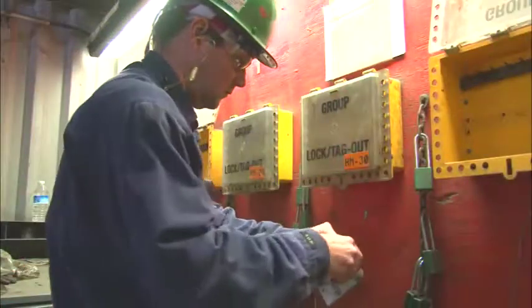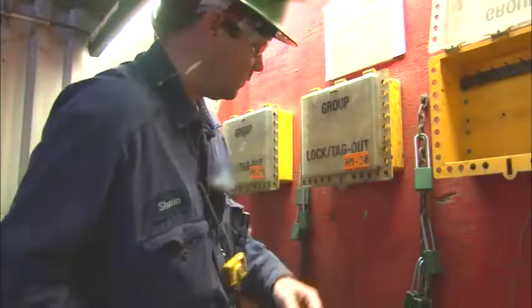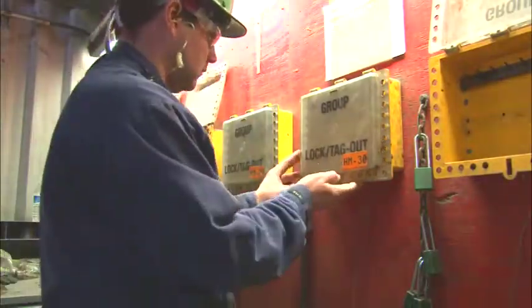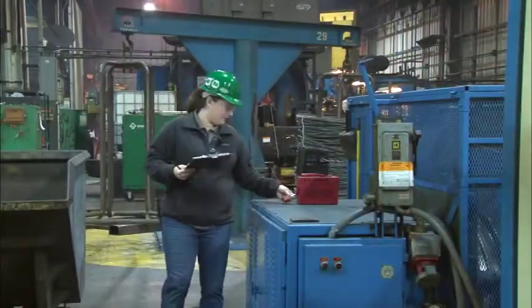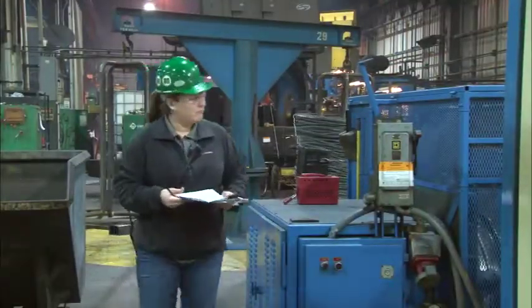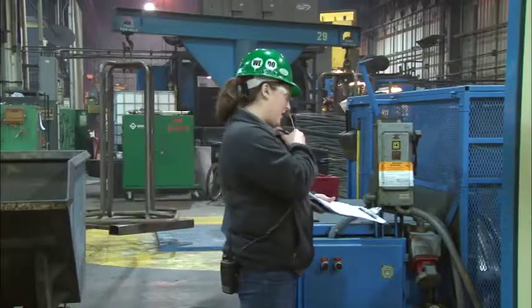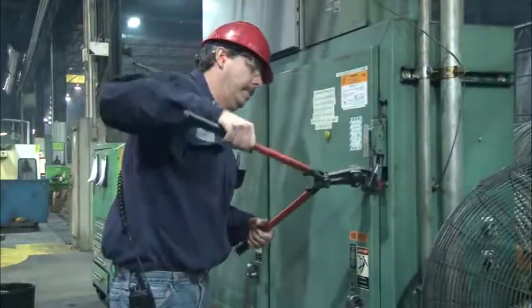Only you can apply or remove your personal lockout lock, and the key must be in your control at all times when applied. If you are not available to remove your lock, your company must verify your absence by making all reasonable efforts to contact you before your lock can be removed by any other individual.